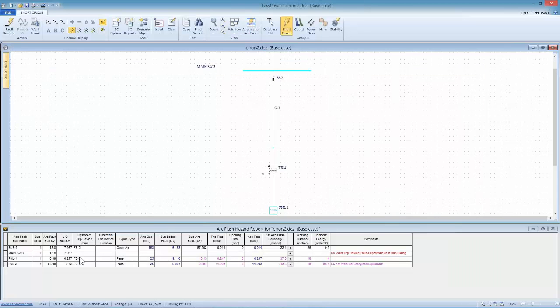Now I see some results. I go back and look at my arc flash hazard report, and what I'm looking for is the fact that every time there's a calculation, I see that the fuse was a protective device in play.